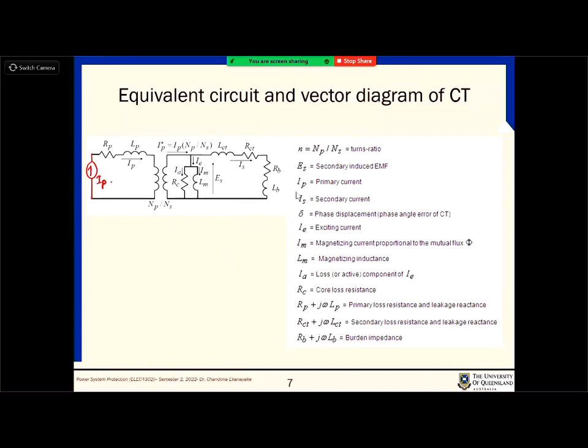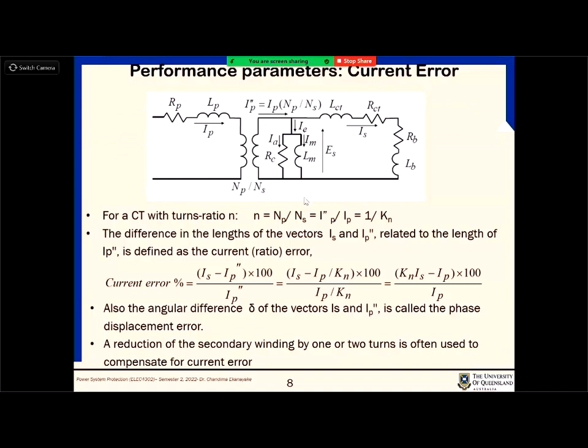So what you need to understand is that these parameters are defined, and in this sort of circuit calculation, one of the things that we assume is that everything is linear. We are working in the linear region. When it goes to the saturation region, then this circuit isn't valid. You can also see that there are losses associated with this circuit, like RC, which is the core loss, and then CT resistance loss, and whatever losses are associated with the primary side. And it is important to understand that there is an error associated with the CTs as well, right?